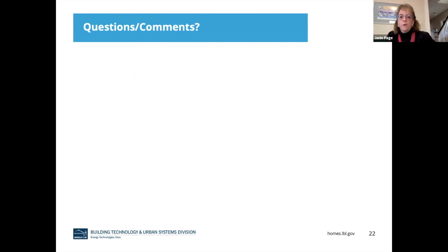That was a great talk. We have a few questions. The first noted that MERV-13 sounds like a reasonable measure, but what about older commercial buildings that have had multiple modifications over the years, impacting airflow and creating air spaces that are not exhausted? Can you give a sense of the kind of testing needed, how to make corrections, and what other measures besides MERV-13 could be implemented? Sure. Beyond filtration, there's just general commissioning in terms of knowing what the system in the building is doing. Typically, that's a matter of measuring air flows. A modern brand new system might have air flow stations built in with nice controls where you just go to a panel and it tells you the airflow, but all systems will not have that.